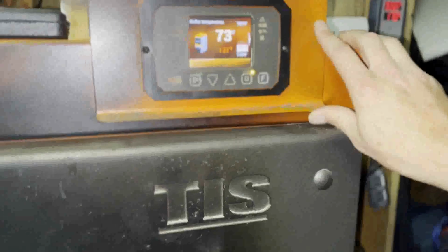But this is all tied together so that if the water's not hot enough, because one of the issues is this is European power. So in the United States, we do 120 volts to neutral or bonded neutral ground. We do 220 hot to hot. So your air conditioner in your home, that's 220 volts, and that would be from one phase to the other phase, so A to B phase. In Europe, they do 220 volts hot to neutral. So I had to get a transformer, and that is that guy. I had to get that to convert 120 to the 220 hot to neutral, like for European, because this is what this runs off of.